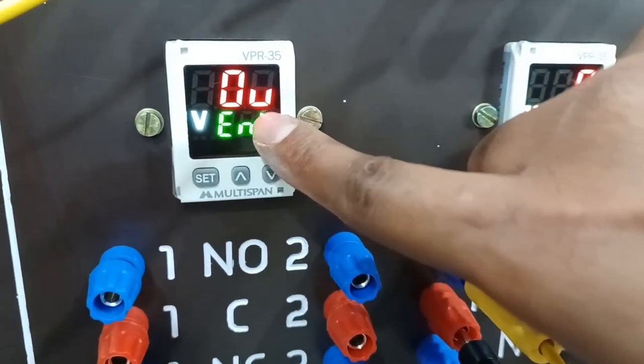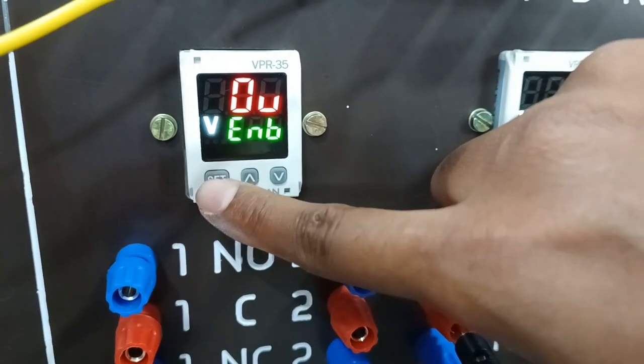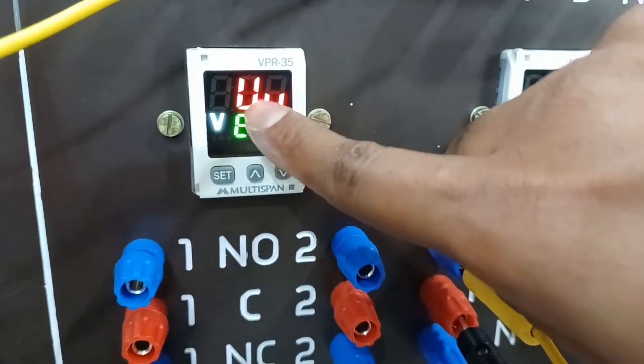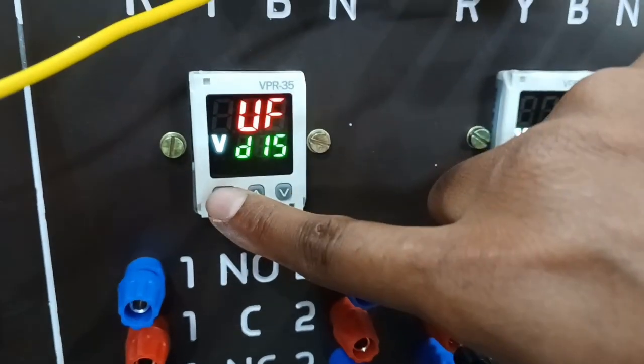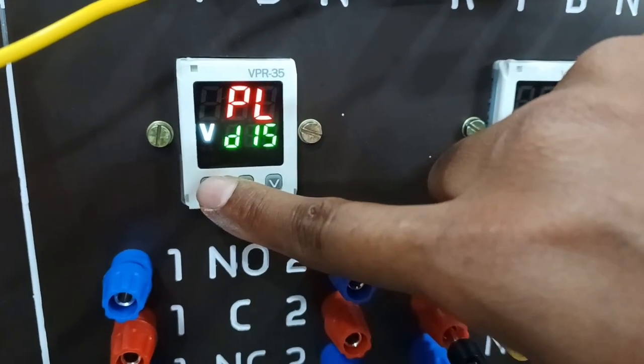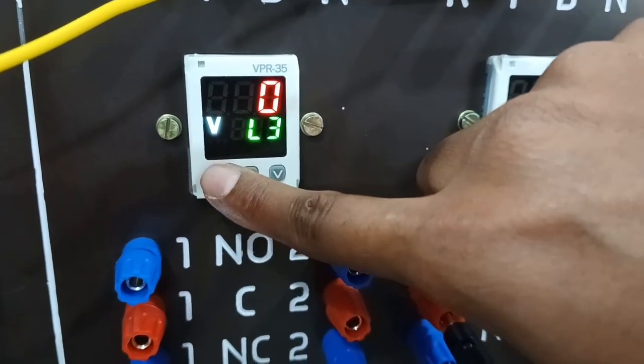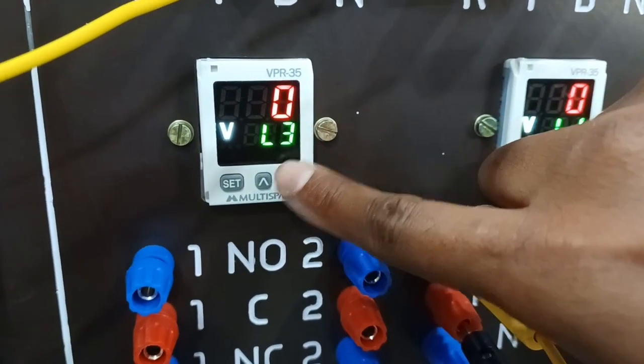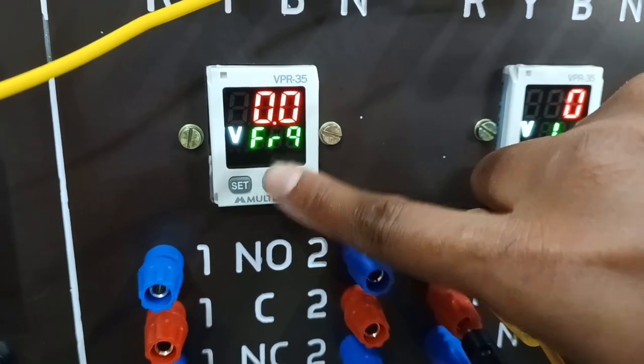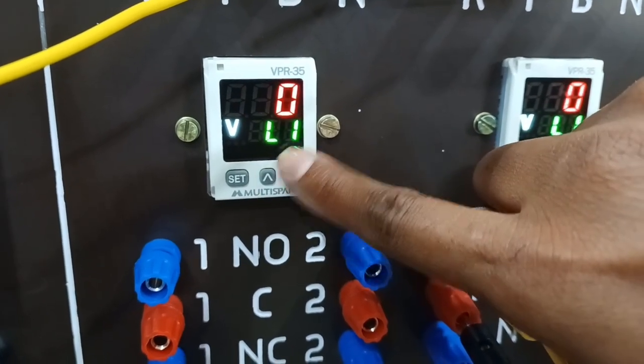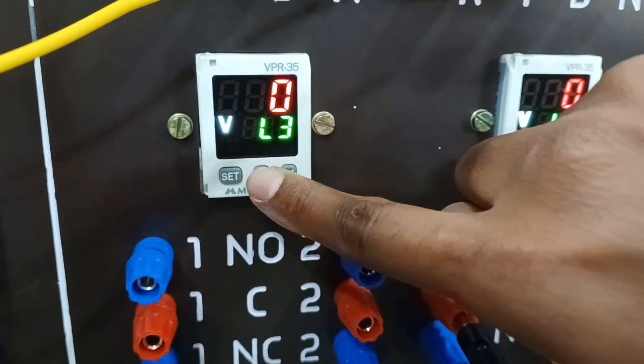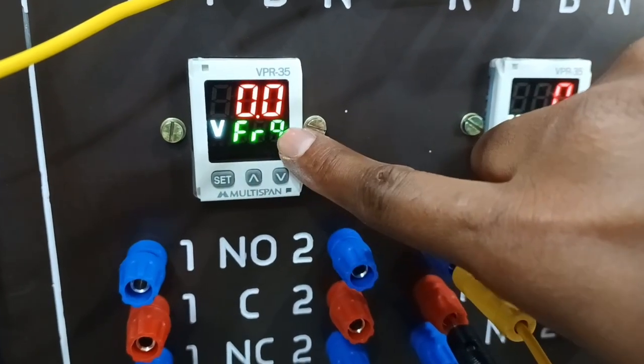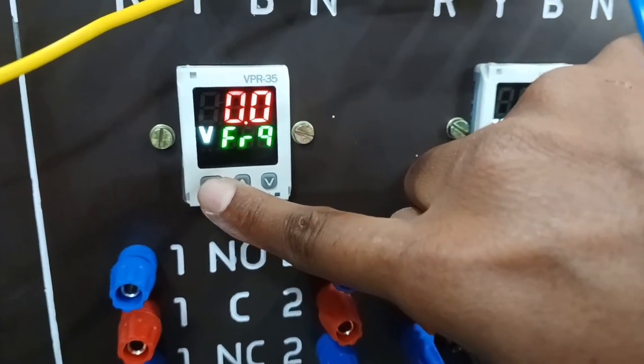Now you can look at the protection functions. Over voltage enable, under voltage enable. Remaining functions are not required. And coming back to main menu, this is our main menu. Now you can look at the voltages: L1 voltage, L2 voltage, L3 voltage, and this is frequency.